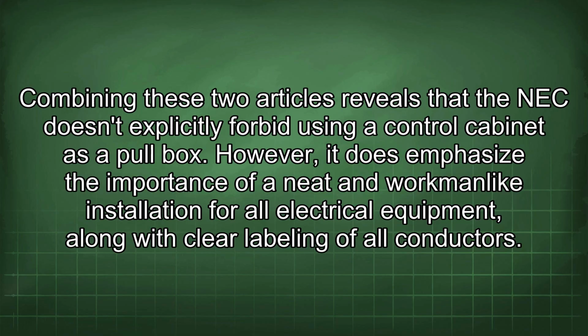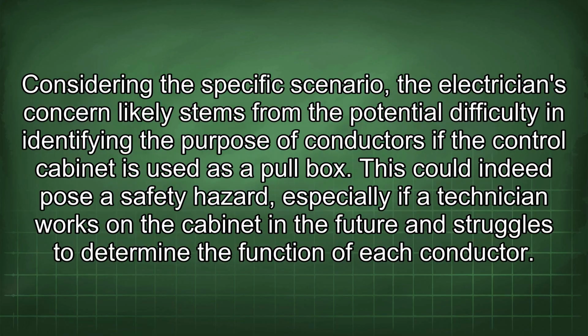Combining these two articles reveals that the NEC doesn't explicitly forbid using a control cabinet as a pull box. However, it does emphasize the importance of a neat and workmanlike installation for all electrical equipment, along with clear labeling of all conductors. Considering the specific scenario, the electrician's concern likely stems from the potential difficulty in identifying the purpose of conductors if the control cabinet is used as a pull box. This could indeed pose a safety hazard, especially if a technician works on the cabinet in the future and struggles to determine the function of each conductor.